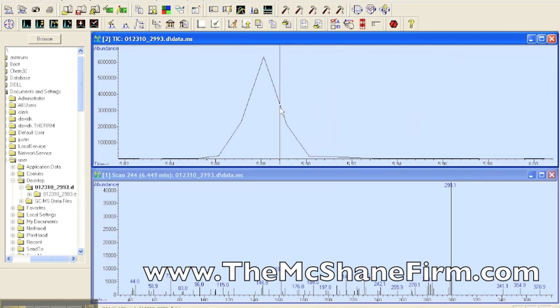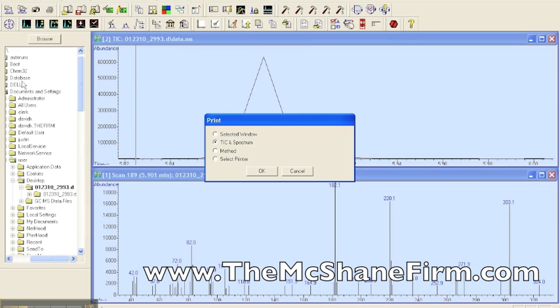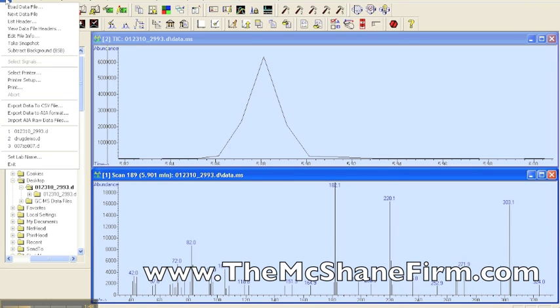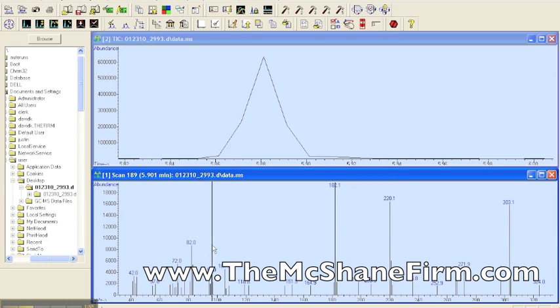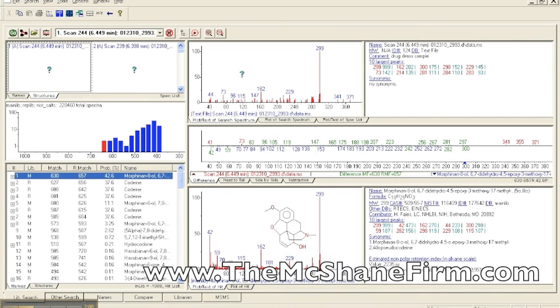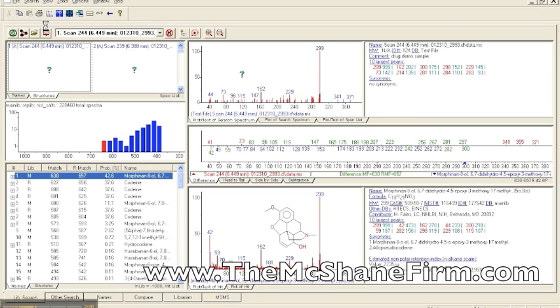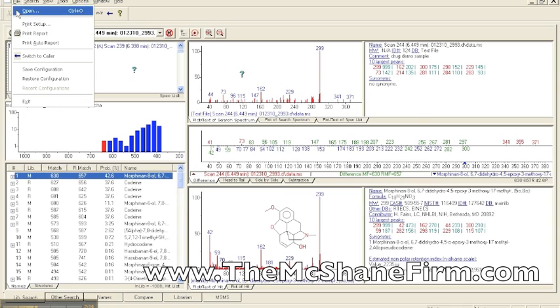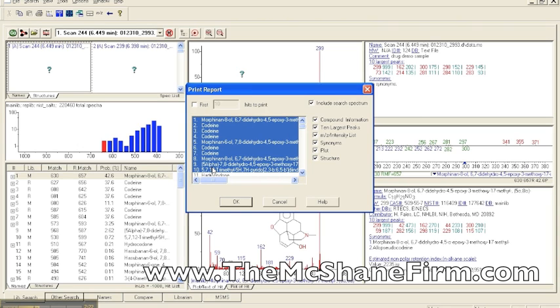Let's see the difference in the reporting styles. So the first thing you would do is hit print. Then you can see here you can either do a selected window, the total ion chromatogram in the scan spectrum, the method itself. Those are different things that can be printed out. And of course you can do different types of prints. You can export data to CSV files so it's open in any Excel spreadsheet, AIA format. But also when you do the NIST spectral library, if you do an auto report you get one sheet of paper and not very much information. But if you go into the print, instead of the auto report, the print report, you can choose the first, you can literally click and choose. And what it will do is it will print out all of the compound information, 10 largest peaks for each one of those. Probably one of the most useful ones that isn't provided to us is this match factor.